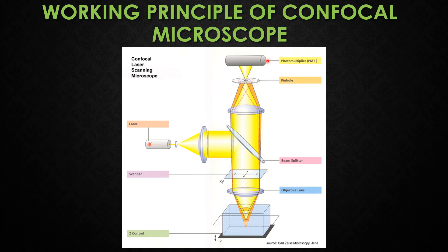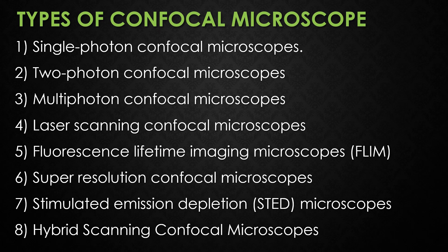The confocal microscope produces very low intensity light, so the light is amplified by a photomultiplier tube, or PMT. These photomultipliers can amplify a faint signal around one million times without introducing noise. After amplification, the photomultiplier tube releases an electric signal which is then converted into an image by a computer.